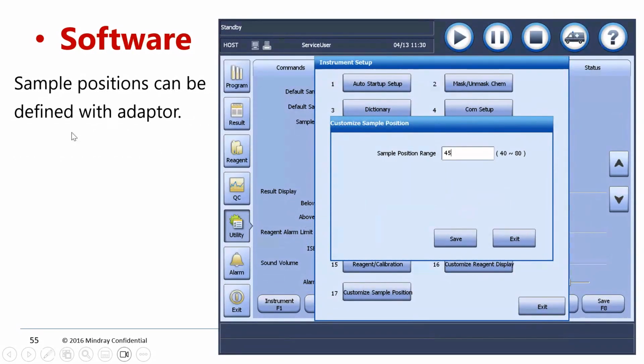Sample positions can be defined with the adapter. As I explained in the reagent compartment, on the outer ring you have 40 positions, right? Those 40 positions you have to use only for the samples. Suppose the customer has more samples and is not using all the parameters, so some of the reagent positions are empty. You can use those areas also for samples. Then you have to configure how many positions are sample positions. You can make it 50, 60, up to 80. That means the outer ring and middle ring you can use completely for samples.